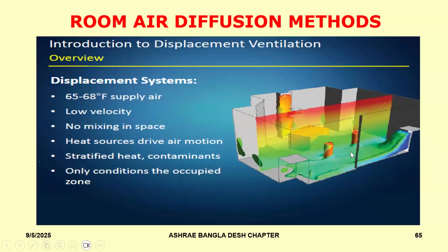And it moves around the room, it goes around the obstacles, and it will stay tight to the floor. The air doesn't mix up. The temperature is lower, therefore it is denser, therefore it stays there till it encounters a heat source. Once it encounters a heat source, it will start to warm up, and as it warms up, the air will rise up. It creates what we call a thermal plume. And this thermal plume will continue to rise, and as it rises up, it draws the room air with it and takes it up to the ceiling, from where it gets exhausted out. So if you see the temperature profile, you will see the temperature in the lower part of the room, the occupied zone, is comfortable, whereas it's pretty hot right up on top near the ceiling.